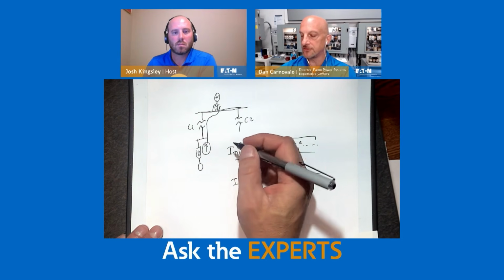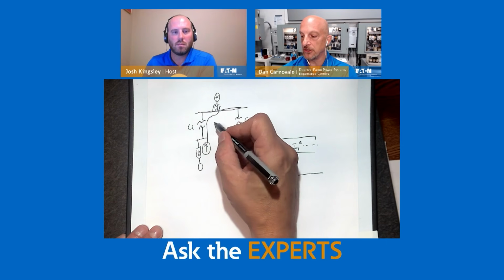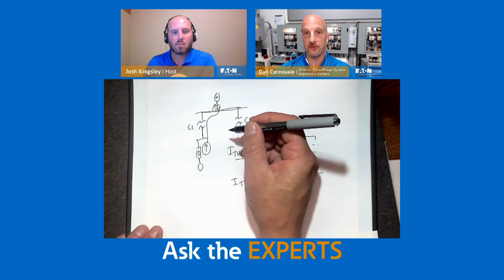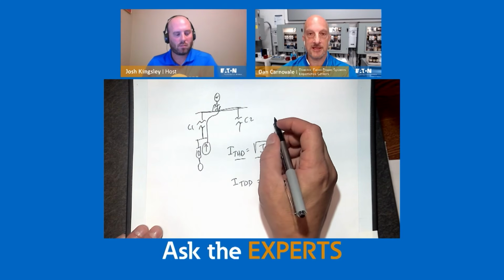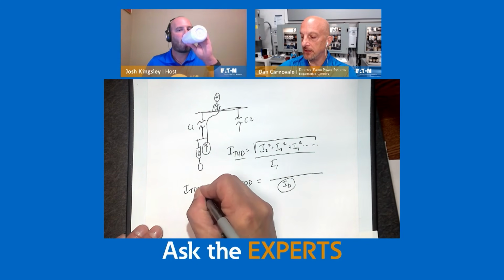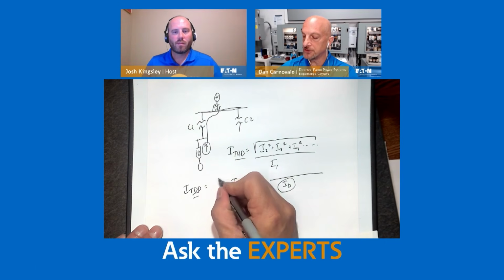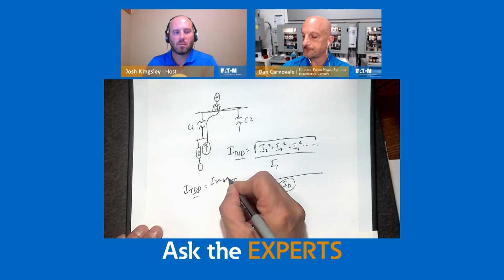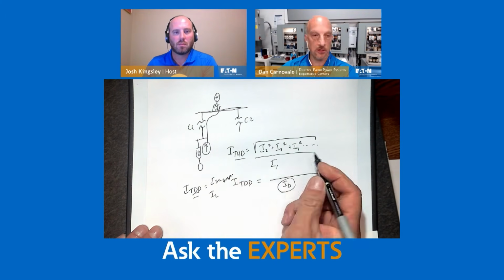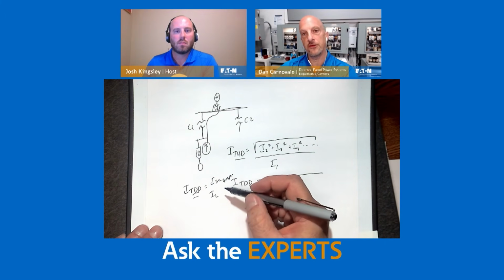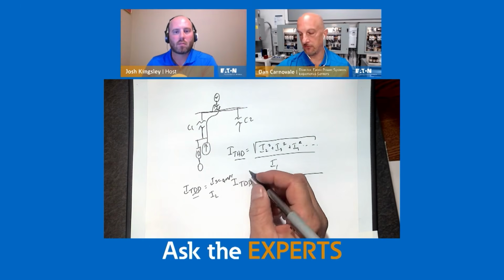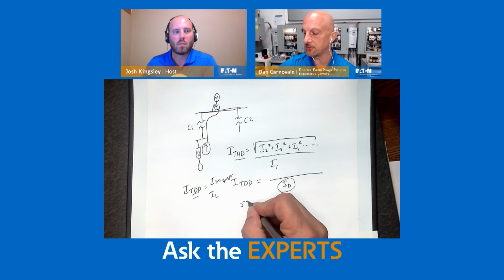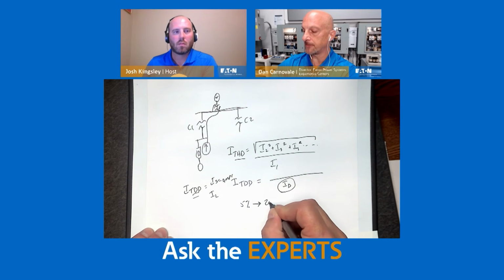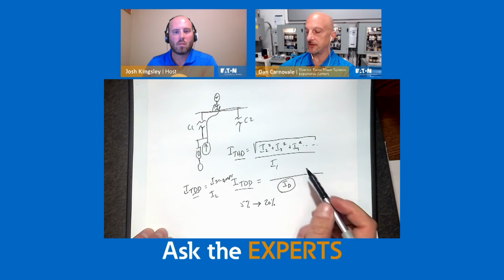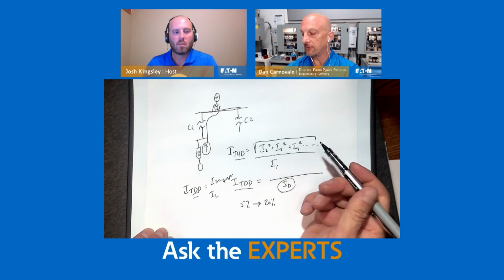And remember the 20% reference I gave earlier? Let's say the load on your transformer, or this transformer, is 50% of its capacity. So they're going to let you produce less. So the ITDD limit is based on your short circuit kVA, so the short circuit amps, I guess, and it's based on your load. And the ratio of those two determines how much distortion they'll allow you. And most of the time, it's between 5% and 20% distortion. So when you look at TDD values in the IEEE standard, that really says I can't screw it up more than 5 to 20% in that range.